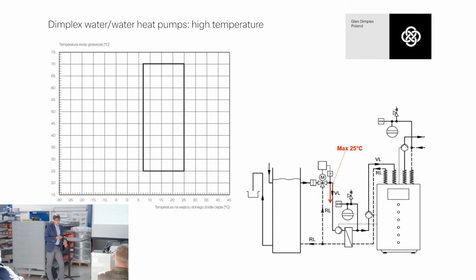Of course, if there is some operating liquid different than typical glycol on that side, we also use heat exchangers between the main loop and the heat pump. This small loop is closed, of course, under pressure with the expansion tank and the safety valve. But the maximum temperature for the supply side is 25, and we always need to remember this rule.